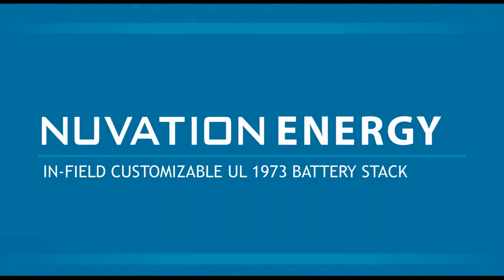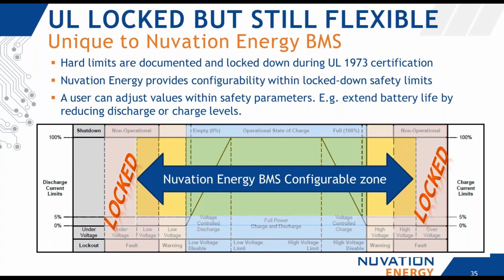And I should also mention in-field customization of a 1973 battery stack, because it's an important part, and I'll explain a bit about that. As part of a UL 1973 test, the overcharge and over discharge tests require the BMS to open contactors to prevent the cell from exceeding the specifications. That's kind of implied. But in our case, the BMS is fully configurable, so it allows those thresholds to be adjusted as part of development. We're able to reconfigure a BMS by just uploading a different configuration file, and that will redefine where these limits are. Well, in preparation for a 1973 test, we need to lock those down.